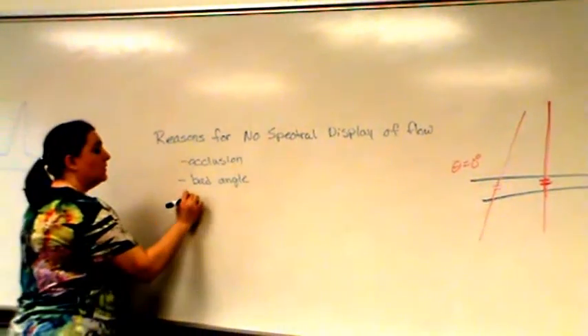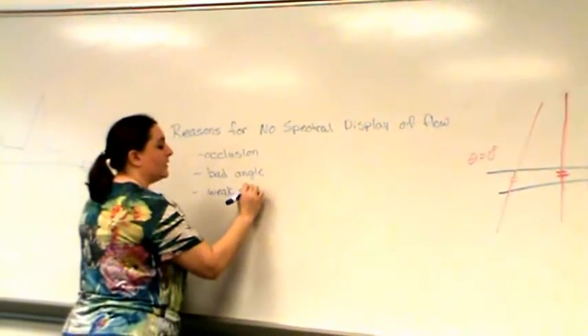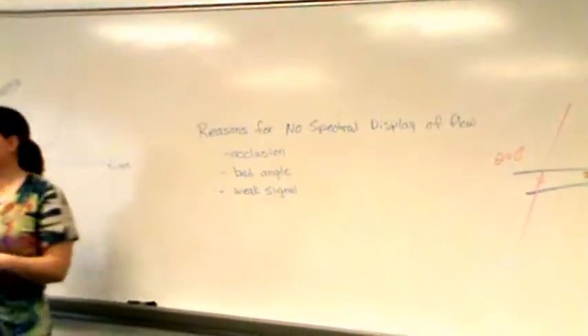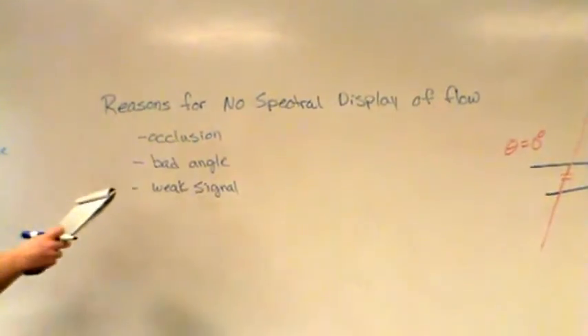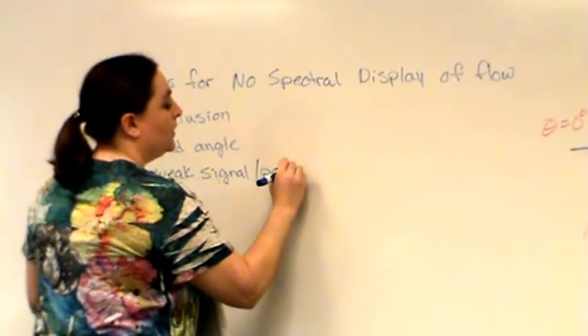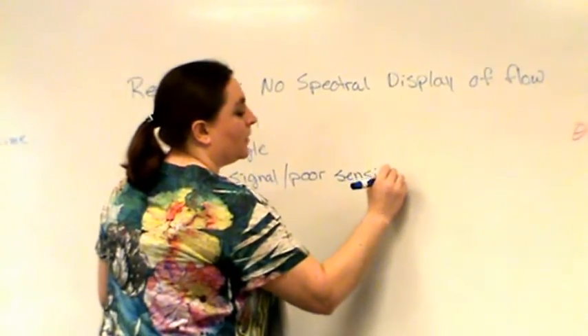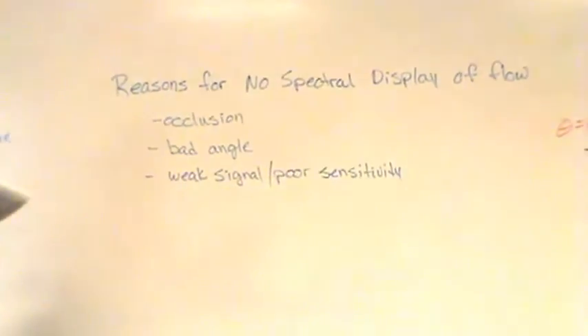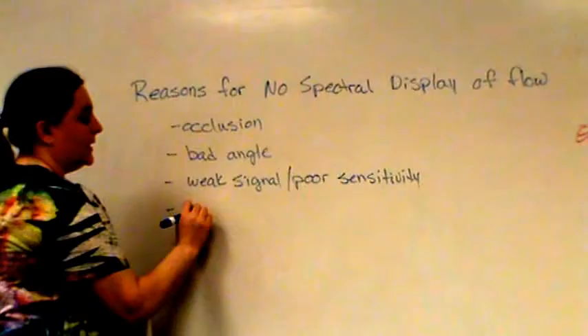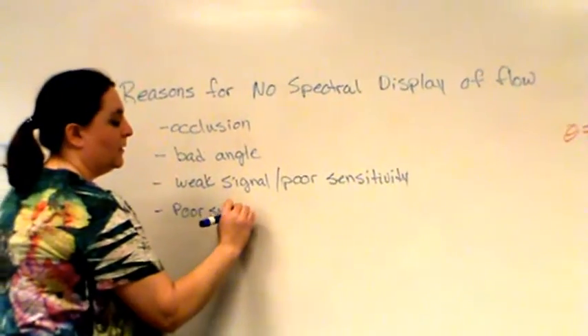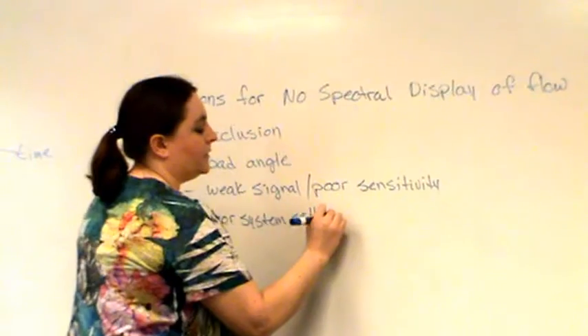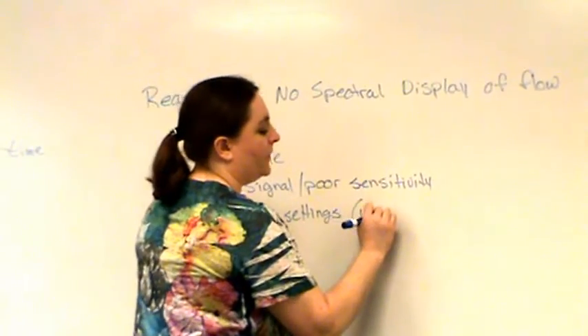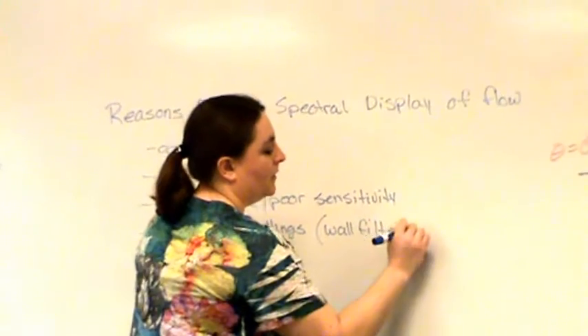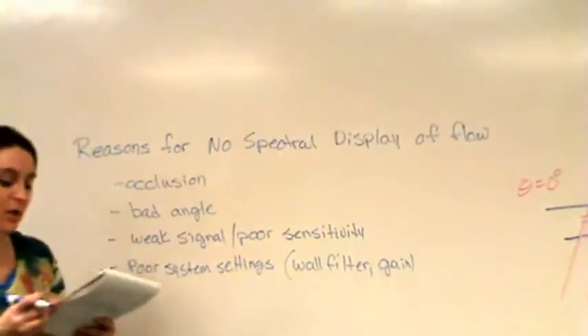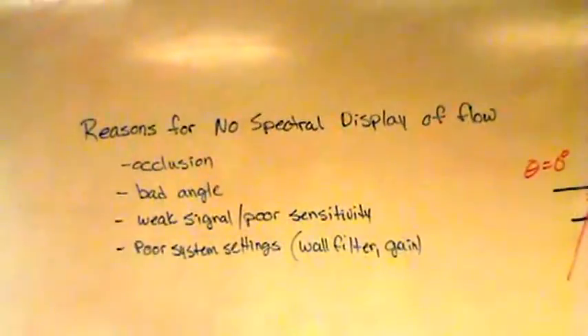A very weak signal. Remember, these are Rayleigh scatterers. So our signal is weak anyway, so if I end up with an even weaker signal, I may end up with no flow detected, or this might relate to poor sensitivity of the system itself. Along that idea, if my wall filter is too high, poor system settings, so things like wall filter or gain. If my gain's too low or my wall filter's too high, I'm not going to have any signal in there.